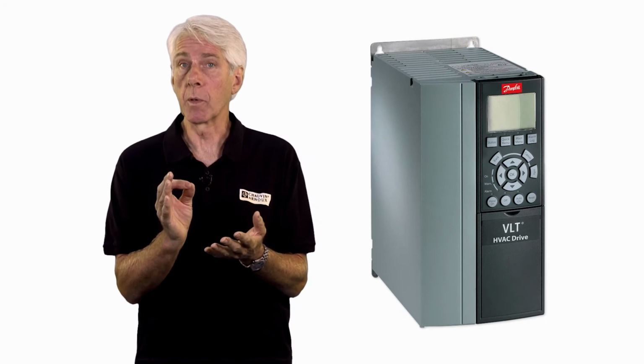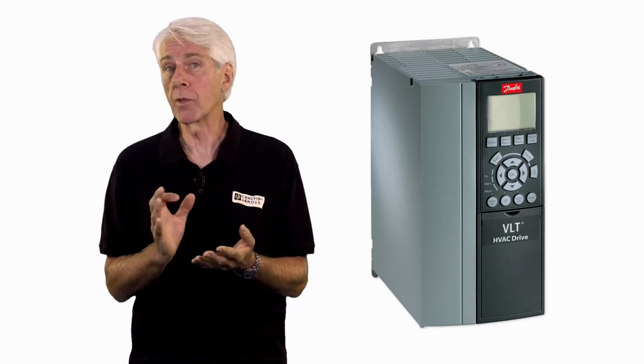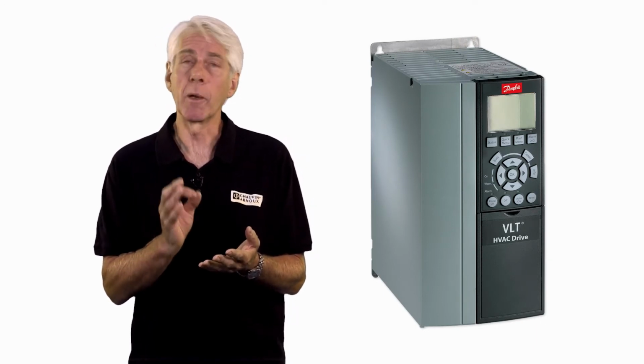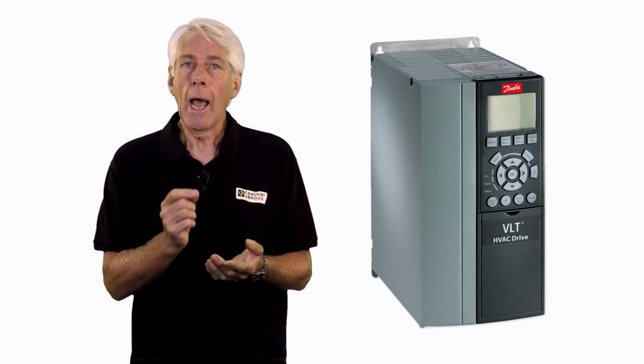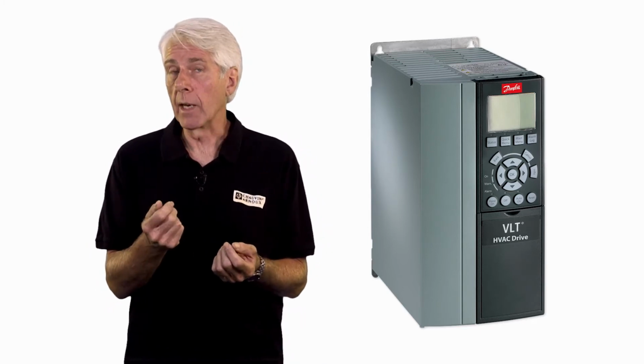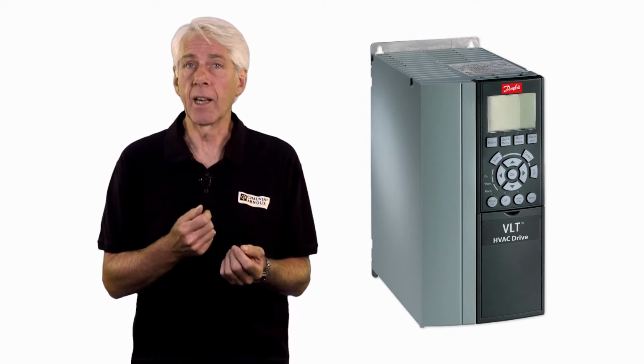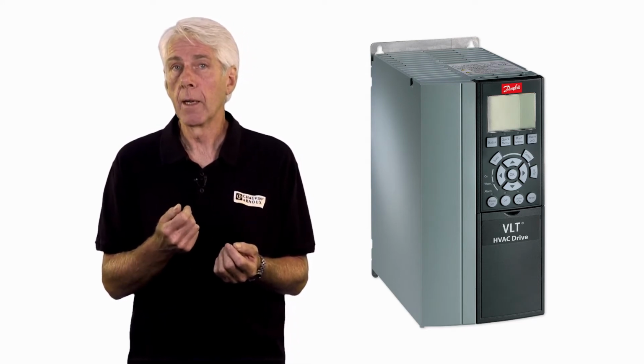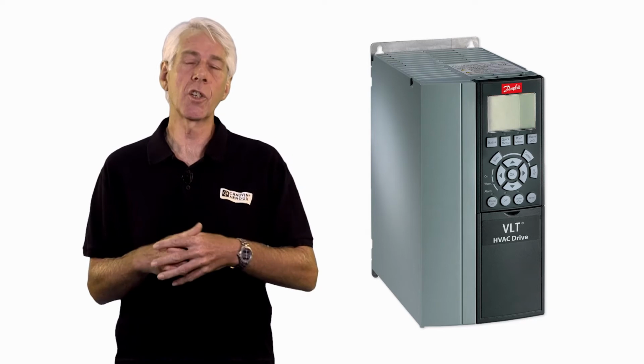It's also the case that older HVAC systems often operate motors at full speed, using baffles to restrict airflow as required. More modern systems, with motors controlled by variable speed drives or VSDs, will reduce motor speed instead. And on the basis that a motor running at 80% consumes 50% less electricity than at full speed, this can be another area where large savings are possible.